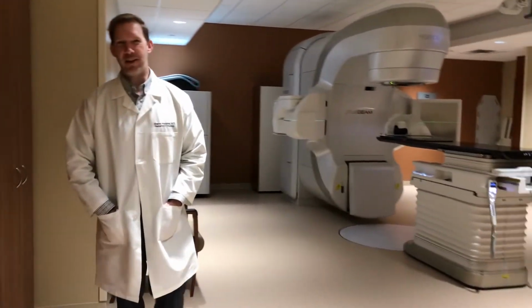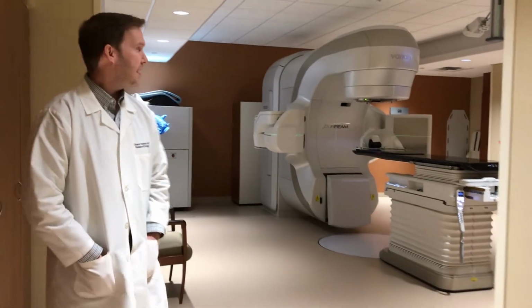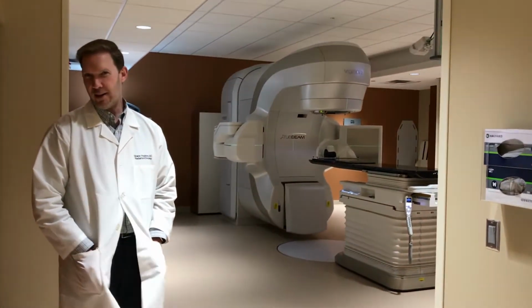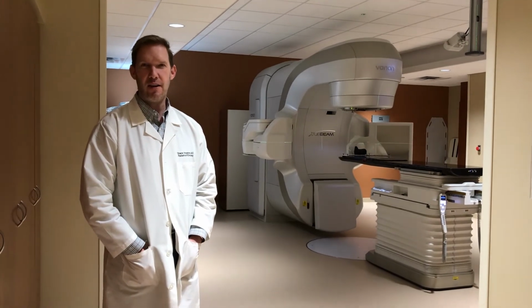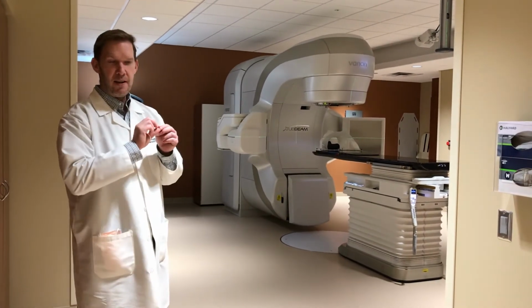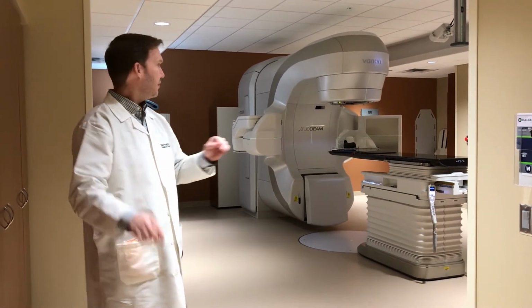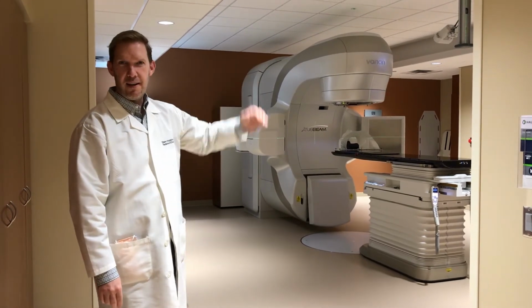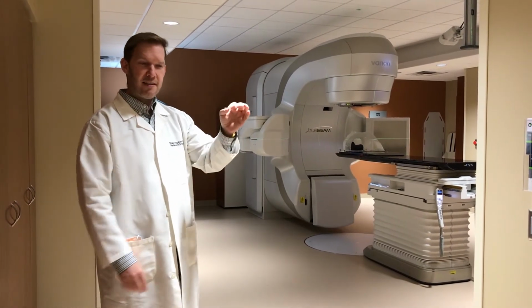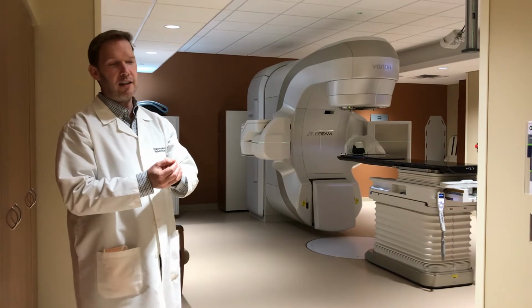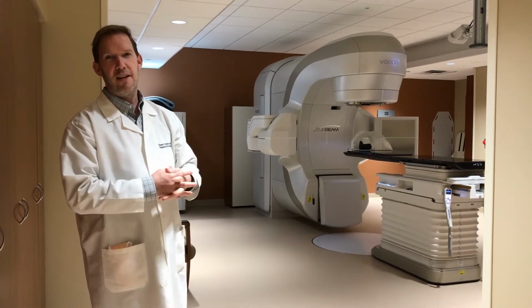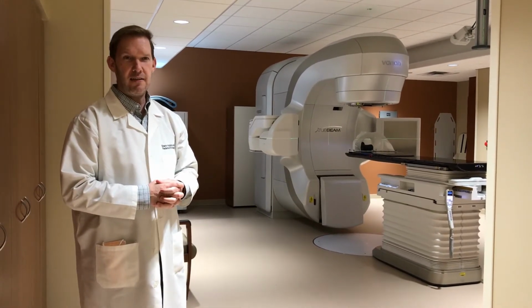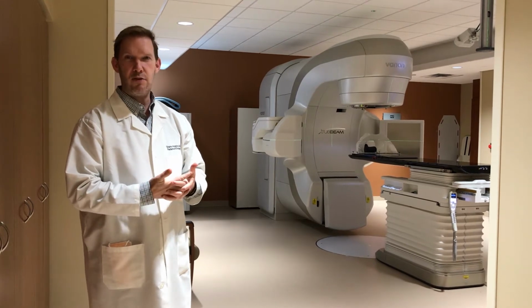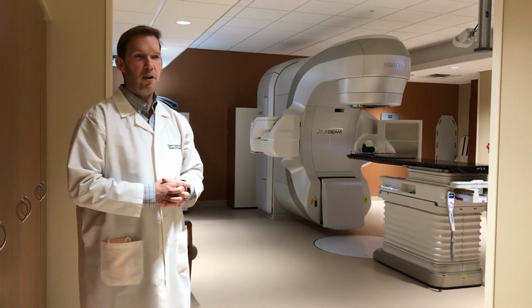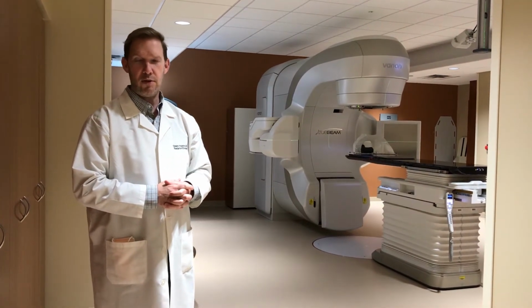And this is our new linear accelerator called the TrueBeam. It is the latest and greatest. It's a fancy machine that will accelerate a pencil beam of electrons through the waveguide in the head of the machine. That goes so very fast as it slams into a tungsten target, it creates a spray of photons. So that radiation is megavoltage X-rays, the same kind that's used for radiology, but we don't use it to take pictures, we use it to treat cancer.